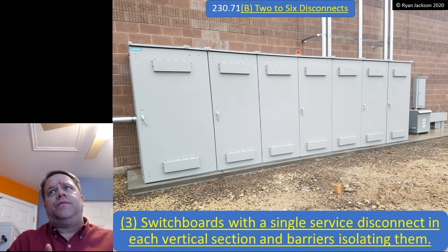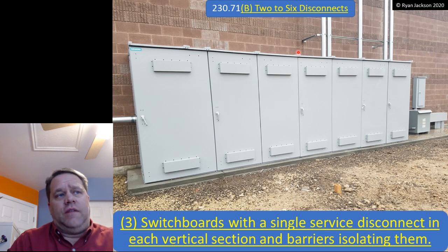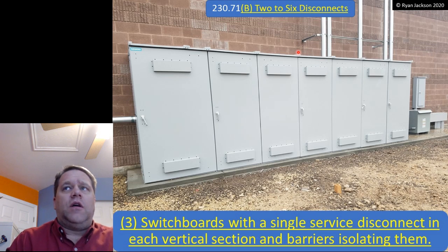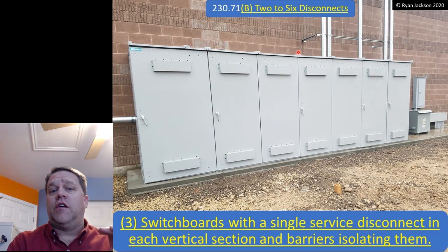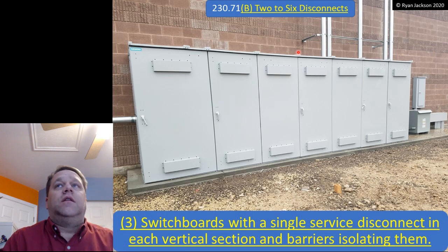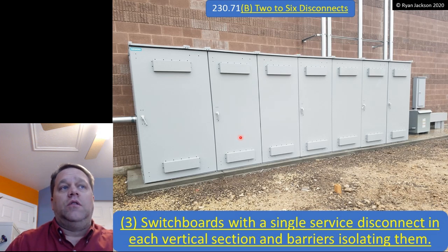By the way, the concern here and why they removed this is for the safety of electrical workers. If I'm in a panel board that has 6 service disconnects inside 1 enclosure, if I ever have to work on that, once again, I need to call the utility and schedule an outage. And I won't be able to have the guards over the terminals like I had in 230.62(C). So that's the idea. This is to increase the safety of electricians. So if you're standing in here, you can work on here.